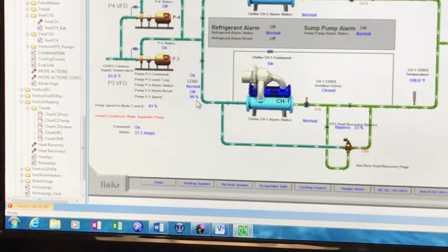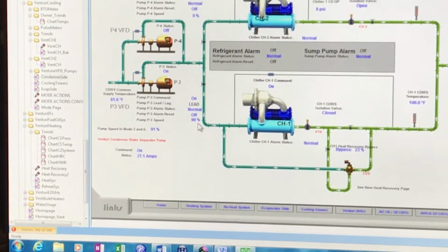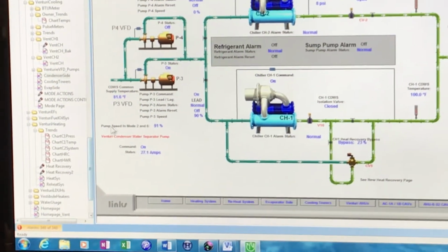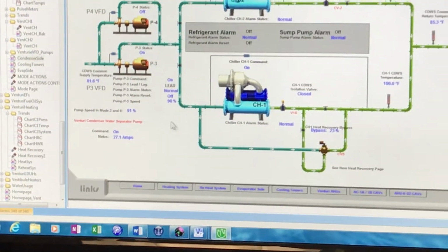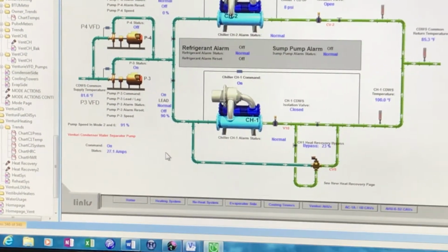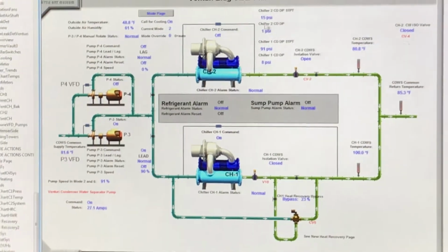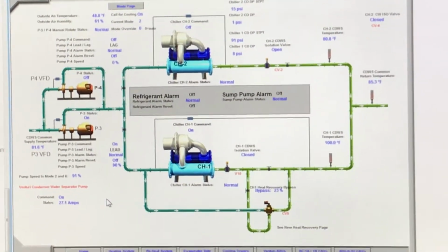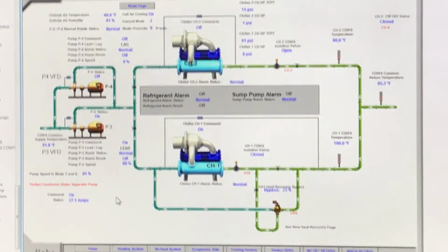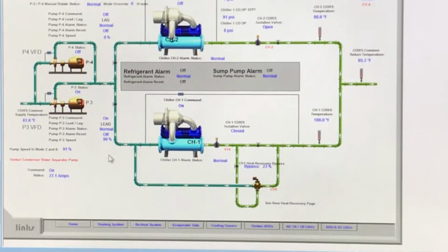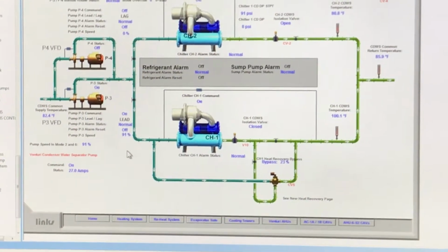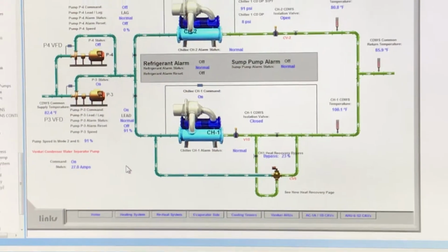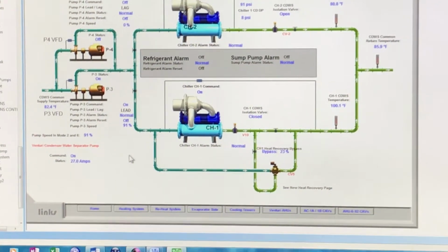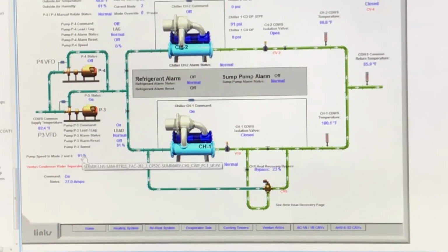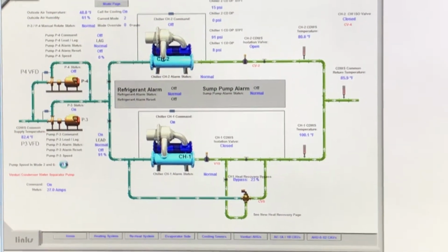And that basically only works when you are in mode 2 or mode 6. All the other modes, this will not work. In mode 1, the pump will not be running. Mode 0 it will be off, but in mode 2 and mode 6, the pump will be running. You are only running chiller 1, and that speed will be controlled to that value. But in modes 3, 4, and 5, it will be controlled to the DP across the condenser barrel of chiller 2.